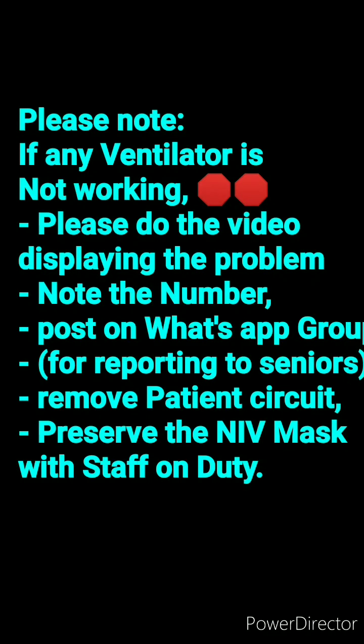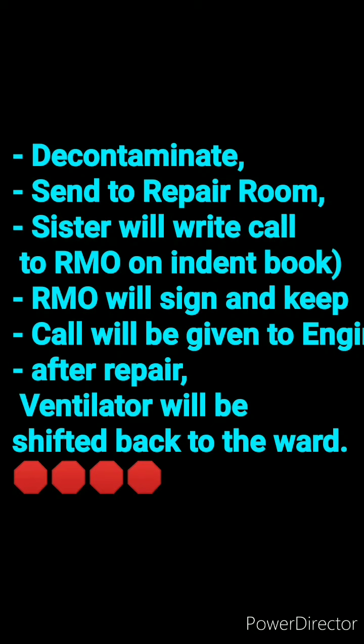If any ventilator is not working, please shoot the video displaying the problem. Note the number of ventilator, post on WhatsApp group so that seniors are informed. Remove the patient circuit and preserve the mask with staff on duty. Decontaminate the ventilator by appropriate measures. Send to repair room. Sister will send in call book to the RMO, and that RMO will preserve the call, and call will be given to the company person, and after repair the ventilator will be shifted back to the ward.